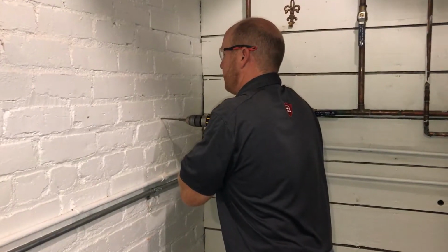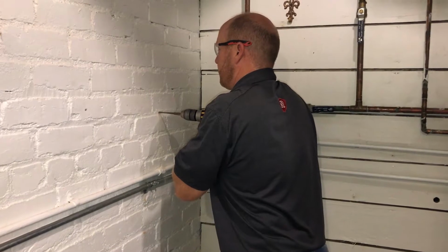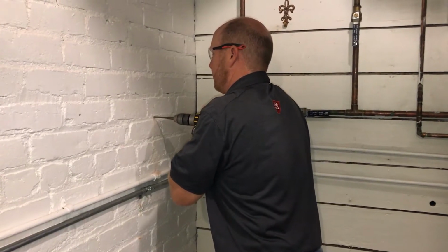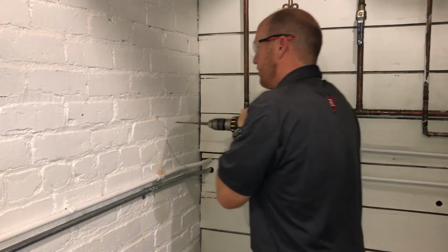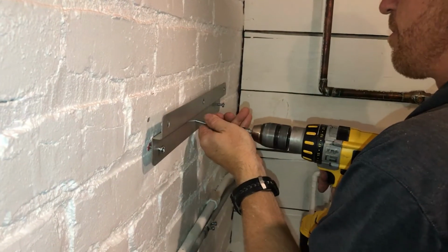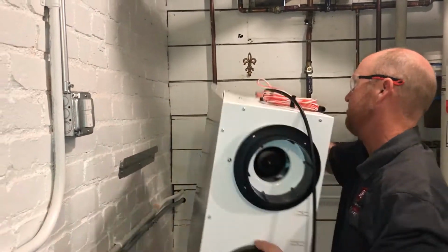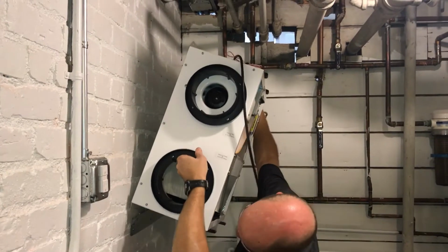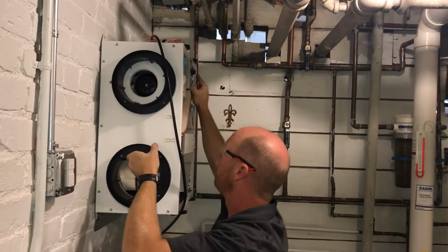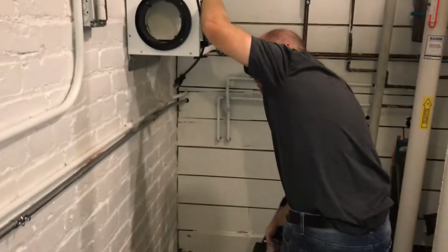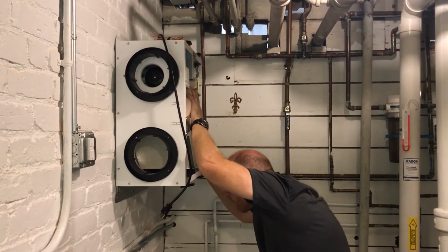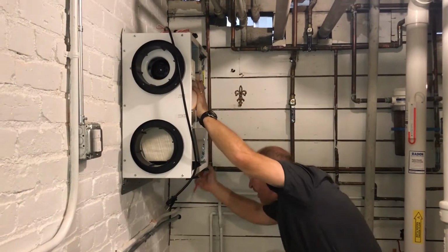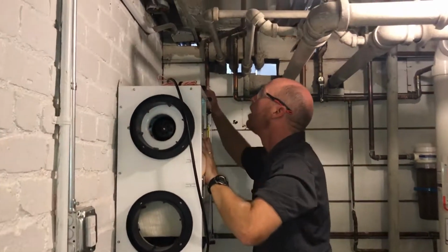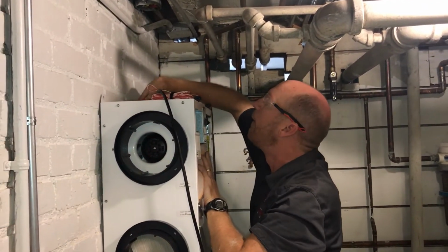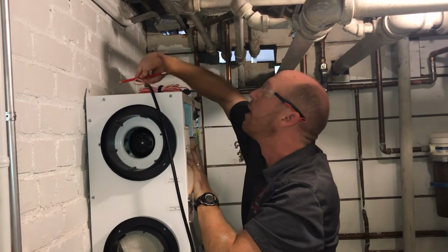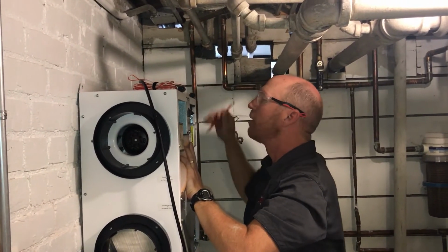So here I'm drilling our initial holes to anchor the unit on the wall. And we're mounting the plate, the mounting plate. Hanging the unit and marking our holes above the unit for the next anchors for the wall. It's important to note that an ERV can be hung on the wall, on a ceiling, sideways, upside down, any way. It does not harm the performance of the unit.